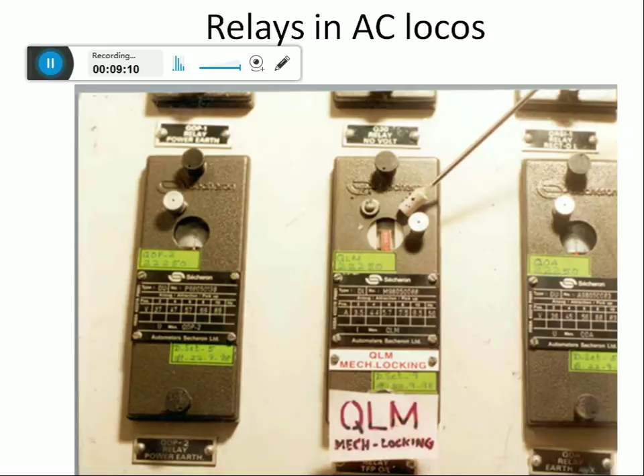QLM is a mechanical locking relay type. You can see, if QLM acted, a red target, a lock indication will be shown on the face of the relay until we examine the loco and reset. Here you can see the reset button. Until we reset, we cannot close the DJ. This target and interlock of QLM on the MTJ branch are interlinked. Until we reset the target, the interlock will not come to the normal position. We cannot close the DJ. So for other safety relays, just like QOP, QRSI, you can see if any relay acted, this target will be shown like this.